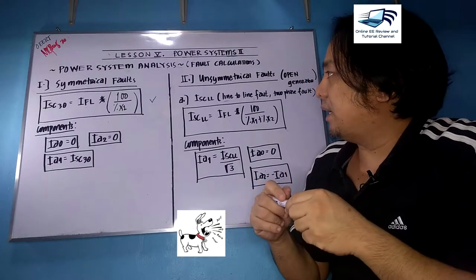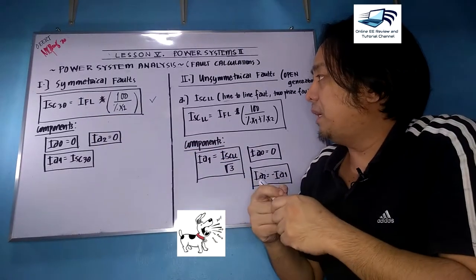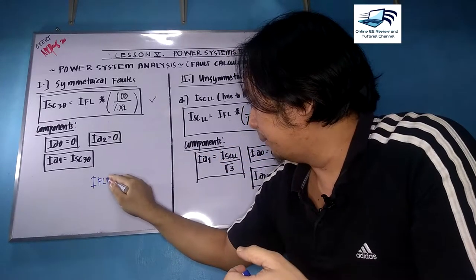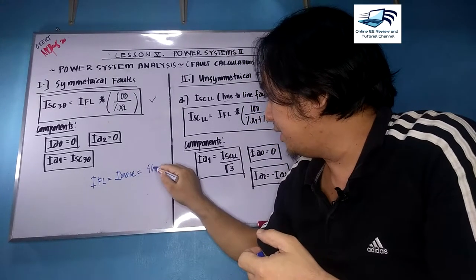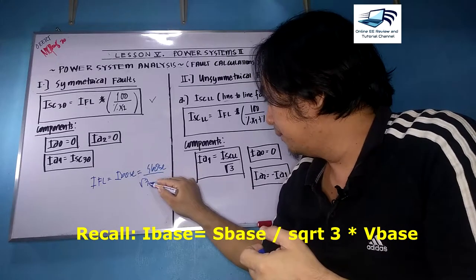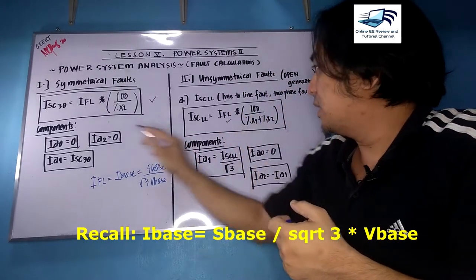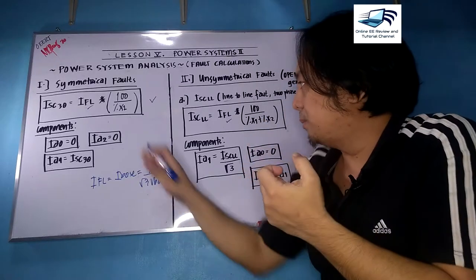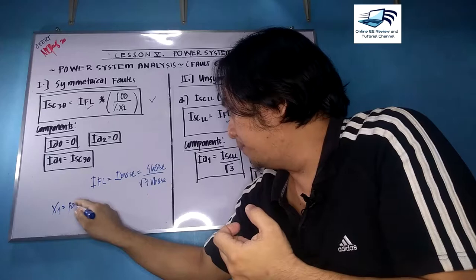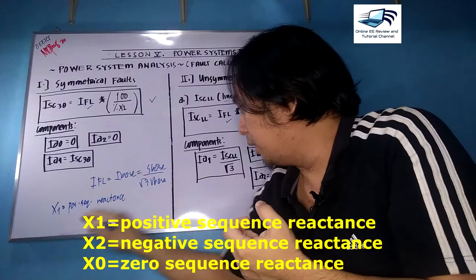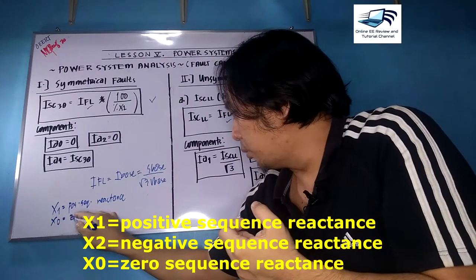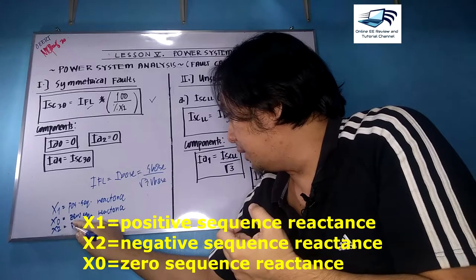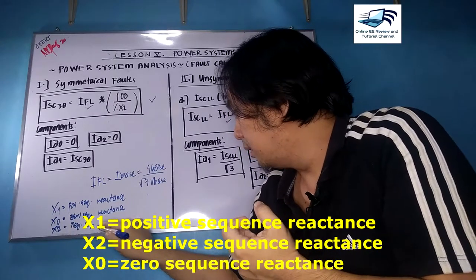For symmetrical faults, ISC is simply equal to I full load times 100 over percentage X1. Your I full load is your base current — I base equals S base over square root of 3 of V base. We also introduce some reactances: X1 is the positive sequence reactance, X0 is the zero sequence reactance, and X2 is the negative sequence reactance.